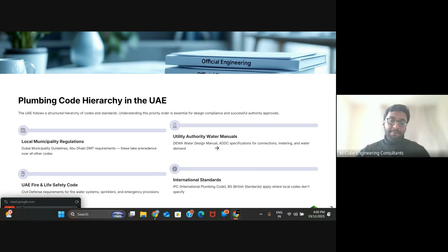Some common reasons for rejection of water supply drawings in DEWA, SEWA, and FEWA include water demand calculations being missed, and overhead tank size not complying with regulations. The authority requires that the overhead tank be half of the underground tank and not more. For example, if you design the underground tank for 12,000 imperial gallons, but show two rooftop tanks totaling more than that, this results in rejection from SEWA.